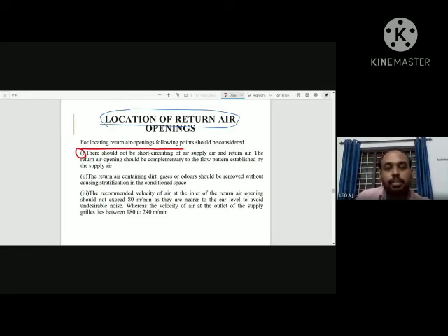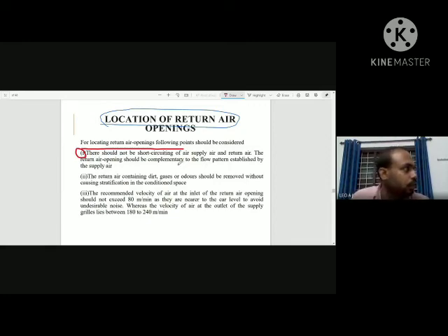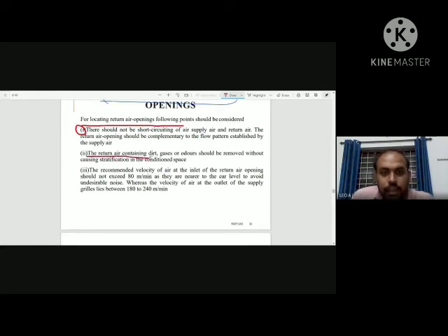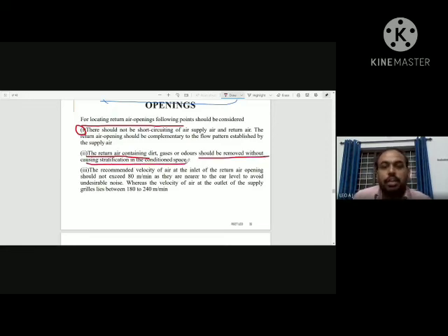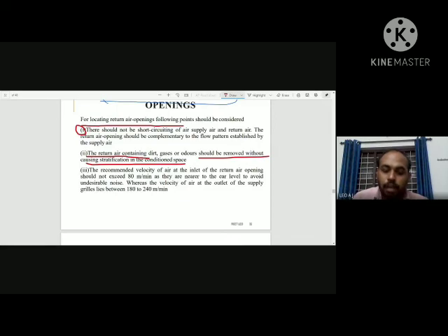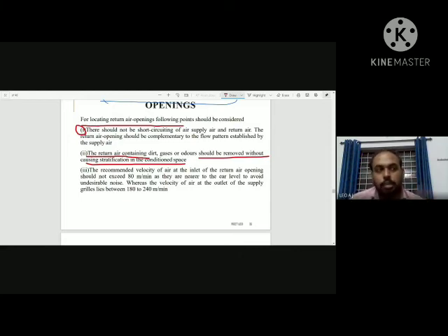The second principle: the return air opening should be complementary to the flow pattern established by the supply air. The return air containing dirt, gases, or odors should be removed without causing stratification in the conditioned space. We place the return air opening so that contaminants are removed before the air is mixed and re-supplied.